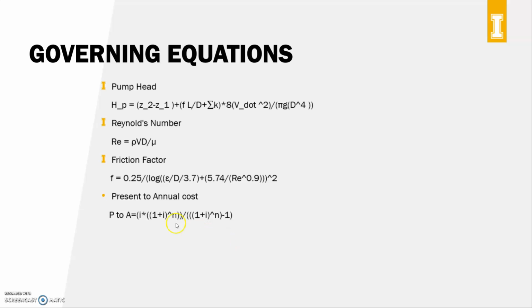Now, the governing equations that we use, the important ones used throughout the project, are specifically pump head, of course, because we're dealing with pumps, and so that's going to be Z2 minus Z1, this is our elevation change, plus our friction factor, times our length over our diameter, times our minor losses. K is our minor losses, and this is multiplied by our V dot in diameter, which gives us our velocity, and this is an important factor in determining our pump head.